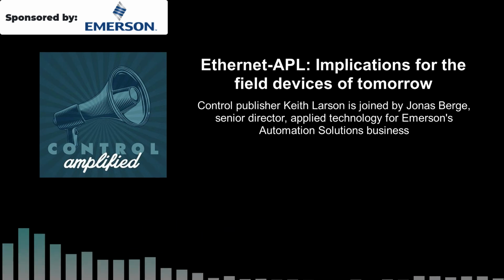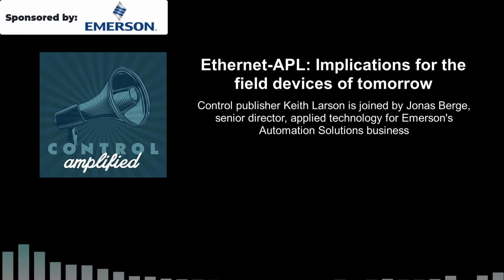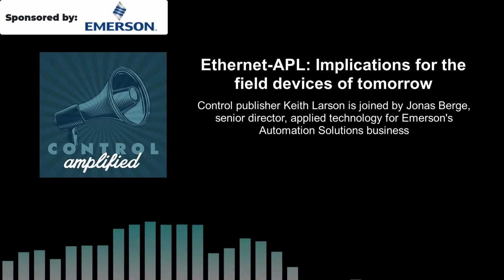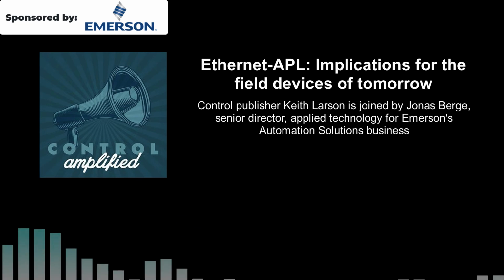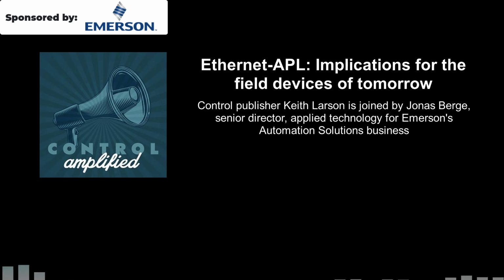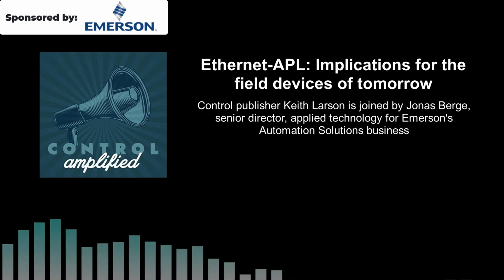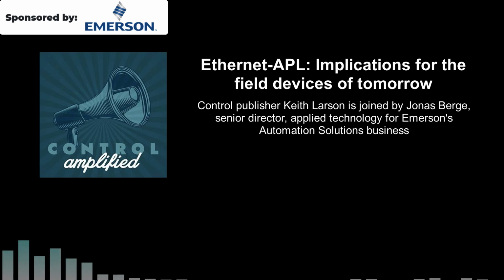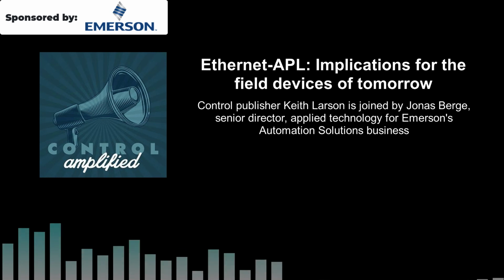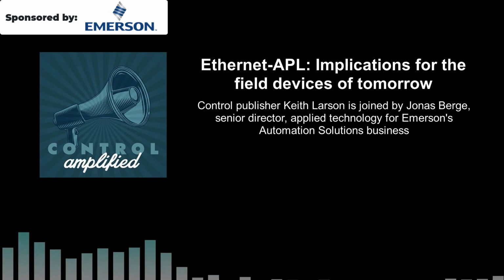So what users should do is, since they're constantly upgrading their DCS every couple of years along with their device management software, make sure that upgrade supports HART-IP, so you can benefit from it in your existing DCS. HART-IP isn't just for APL devices, it can be used in HART multiplexers that some plants have, and it's also used in wireless HART gateways. So don't wait until you're building your next plant; upgrade to HART-IP in your existing plant. Many users actually already have HART-IP, but don't even know it. It's just ticking away in the background in all of their wireless HART gateways.